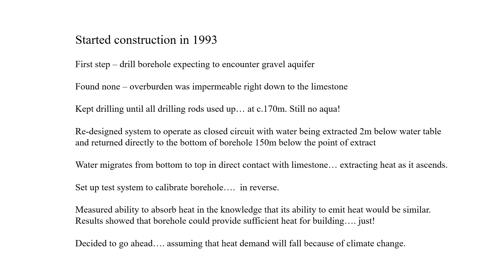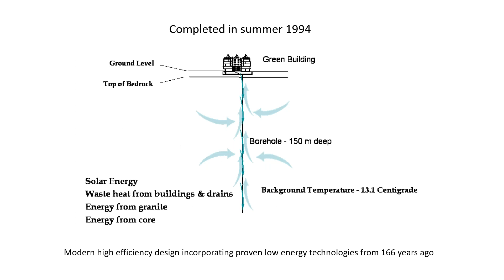We tested it by running it in reverse. In other words, by trying to heat the limestone and measuring its ability to absorb heat, and we assumed that its ability to emit heat would be similar. We reran our design calculations, including dynamic simulations, and satisfied ourselves that there was just enough heat available from the borehole to heat the building.